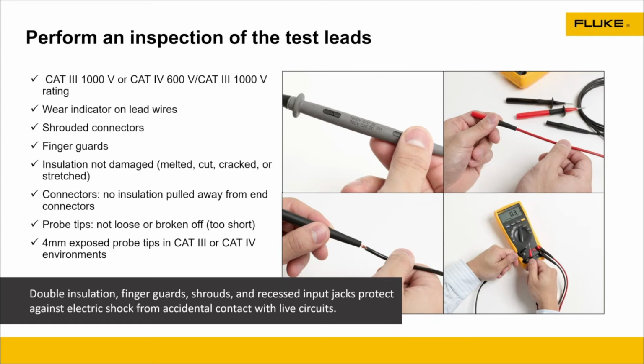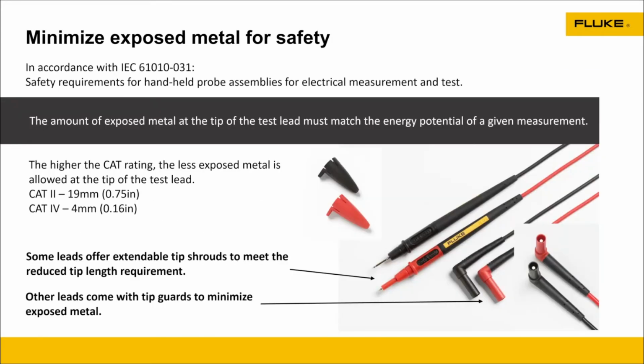One of the key conversations on this is the exposure of the probe and what category rating it puts you in. If you have exposed metal on your test lead like that, it lowers your category rating. You really can't handle that 1,000 volts at that category 4. You're now 1,000 volts category 3 or even category 2. So that's where caps come into play. That's where maybe a tip guard, something that minimizes the exposure of the metal at the end of your test lead, comes in. That way we don't create that arc fault or that arc blast, like in that original picture where we saw the two test leads running across and causing that blast. So just make sure that you're using your test leads correctly, you've inspected them, and they're category rated for your environment.